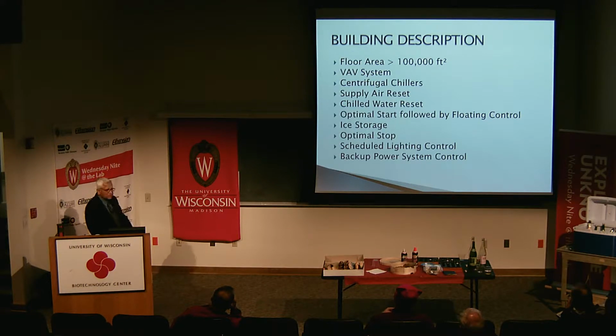Now, optimal start followed by floating control. This is nothing but an optimization program which determines the best time to start your chiller and the air handling unit in the morning, such that you reach a certain temperature that you want at the beginning of occupancy, which could be 8 o'clock in the morning. So in this case, for the demand response, if the temperature band of comfort is, say, 73 degrees to 78 degrees in the cooling season, the optimal start is started such that, with occupancy at 8 o'clock, the temperature will be at 73. At occupancy, if it is at 73, then you reset the set point of the occupied zone thermostat to 78. So there is a certain floating time you have from 73 to 78, during which you will not use the chiller. That results in chiller savings.